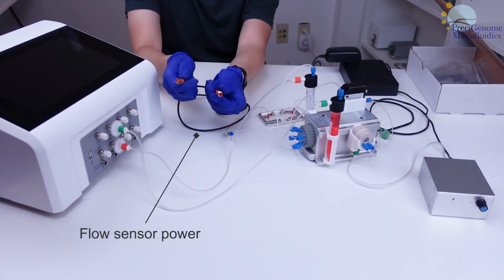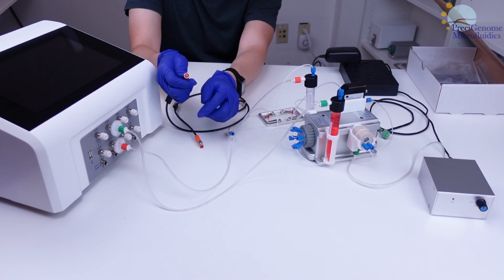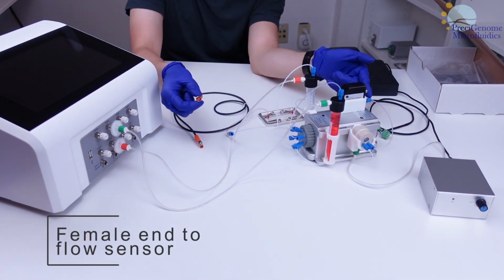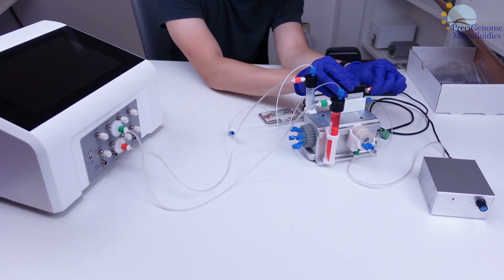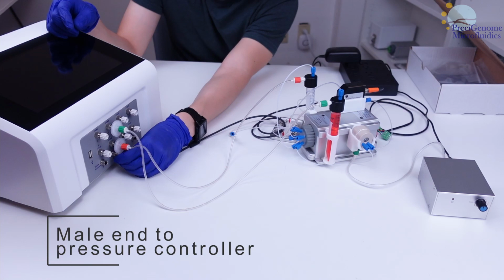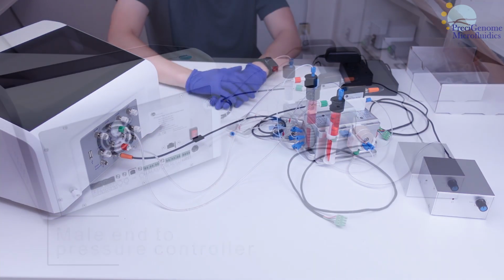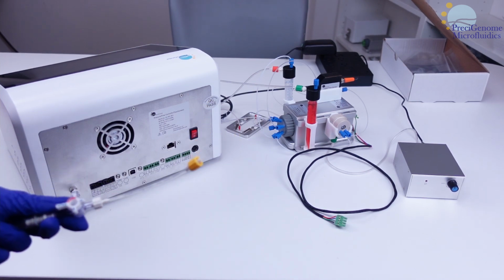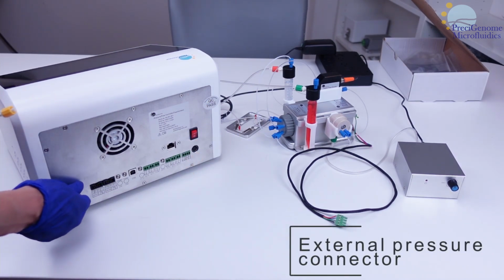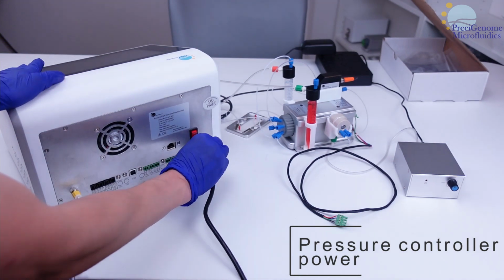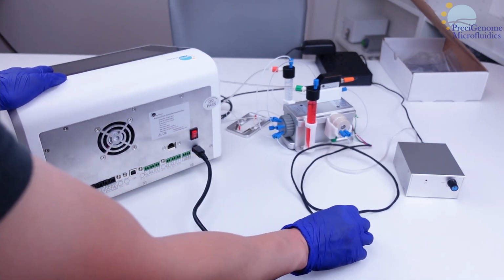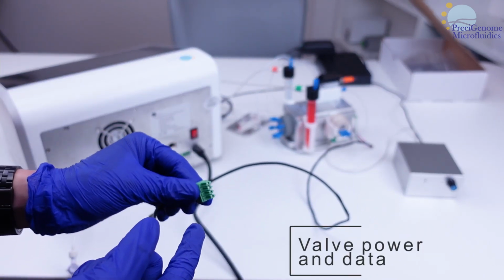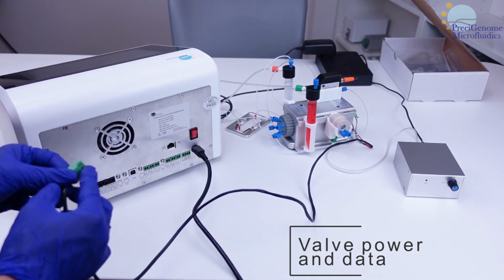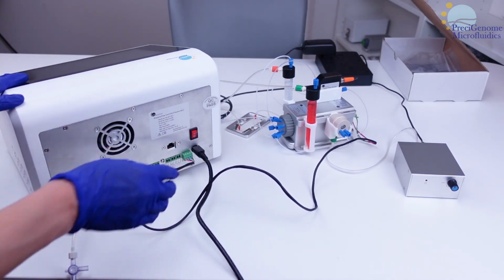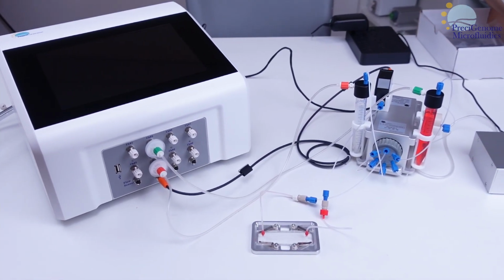Now we can connect the flow sensor to the pressure controller. Take out its power cable and note the ends. The female end goes to the flow sensor, and the male to the pressure controller. If using an external pressure source, you may connect it to the rear of the pressure controller. Next, connect the pressure controller power cable. Finally, connect the rotary valve to the pressure controller with this 4-pin port. Congratulations! You've successfully assembled a recirculation system.